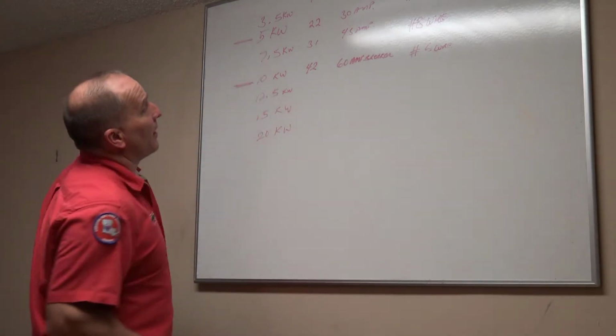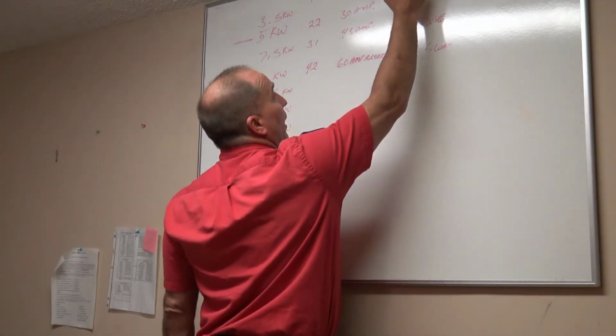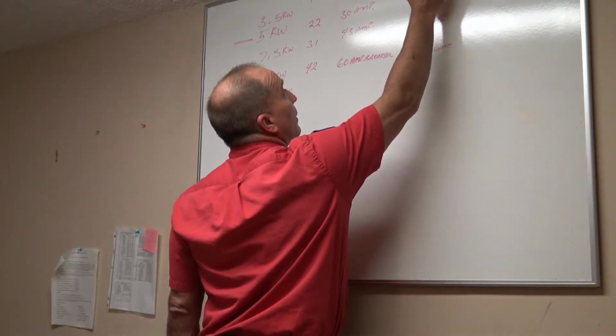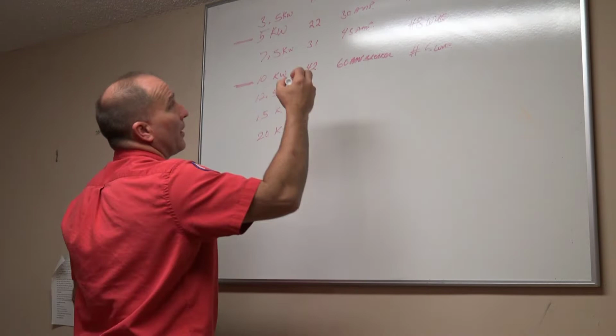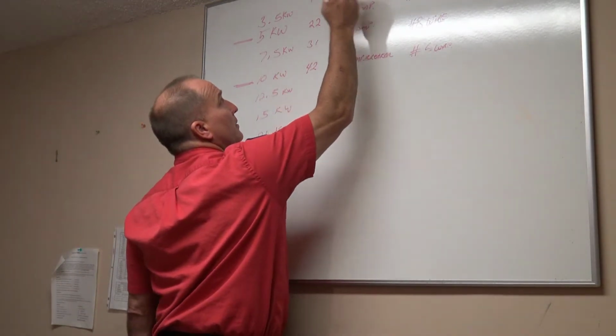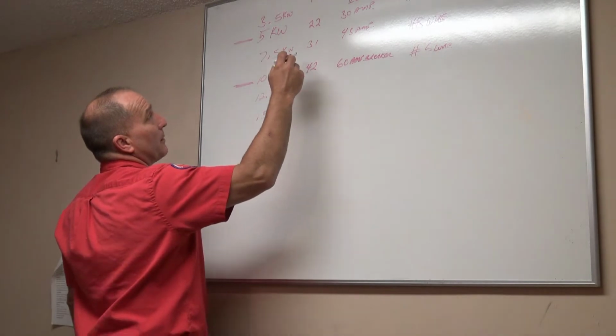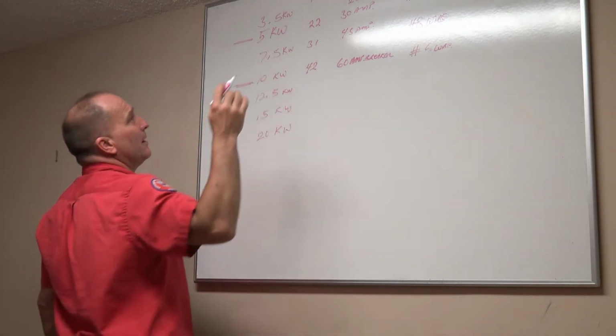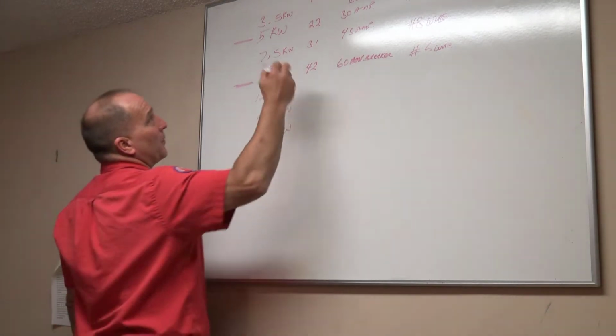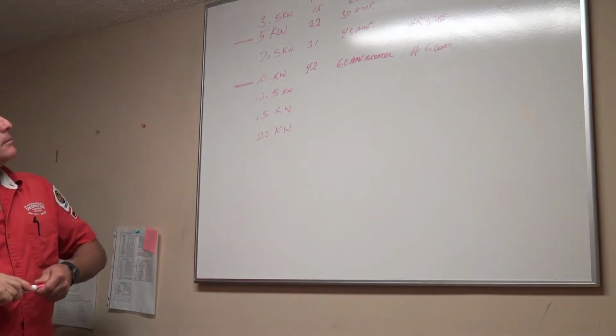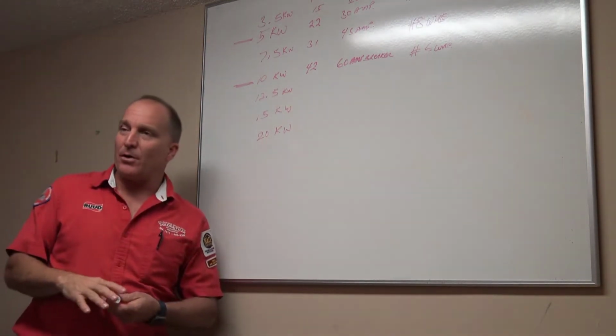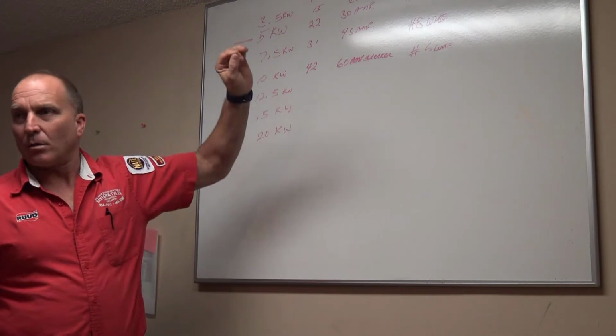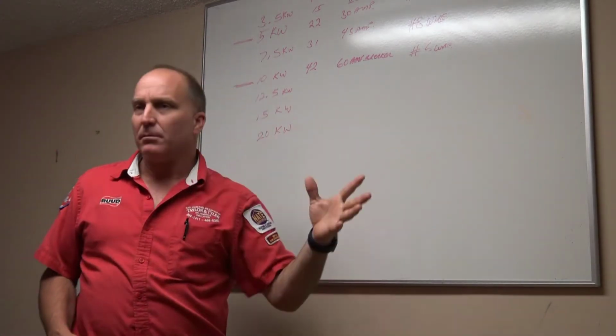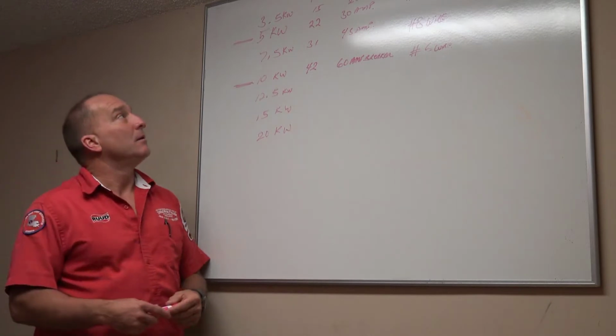All right, well, let's step up this way now. We're going to go to a number 12 wire. What amp breaker here? Well, number 12 wire holds 20 amps. If I'm going 31, 22, 80% of 20, I'm going to call it around 15 amps or so, 14 amps, in that ballpark area, right? Okay, that's about what it's going to be. Remember, you don't have to be exact. If you want to be exact, go to Ohm's law: 242 volts with 3.5 kW heat is 13.6 amps. Okay, big deal. It's about 15.